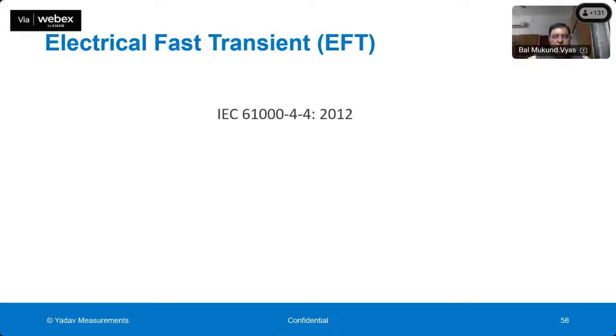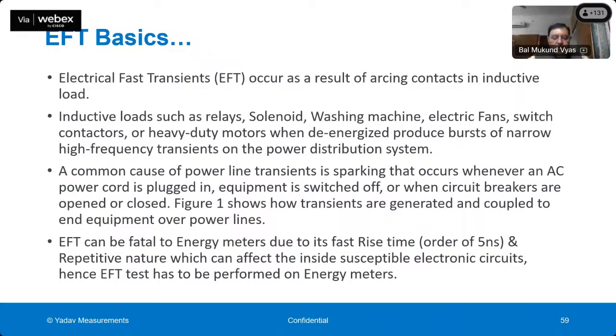Another test is the electrical fast transient test. When meters are installed on an electrical network and switching occurs, especially in grid situations where you have circuit breakers and isolation devices, fast transients are generated on the electrical network and can travel through cables to the meters. Relays, solenoid valves, washing machines, electric fans, switches, contactors and heavy duty motors can all generate transients which can damage the meter or affect its accuracy.